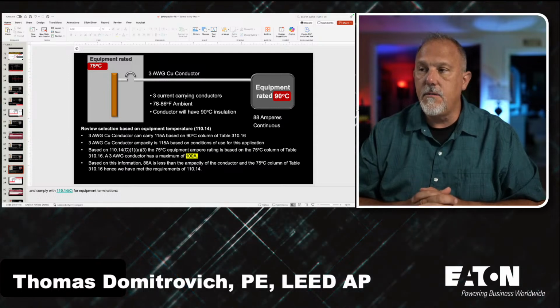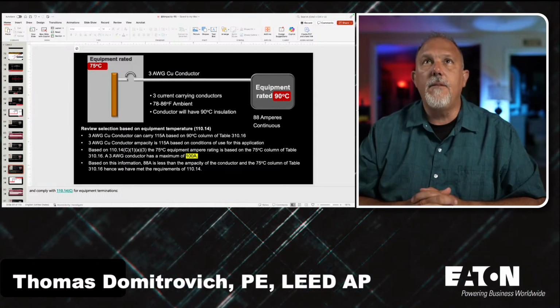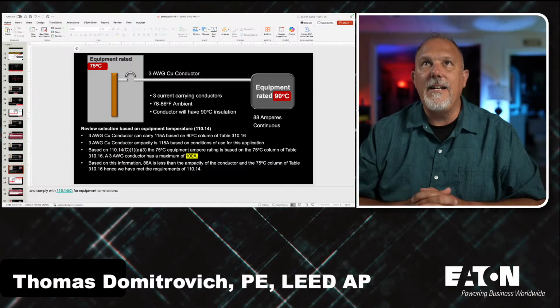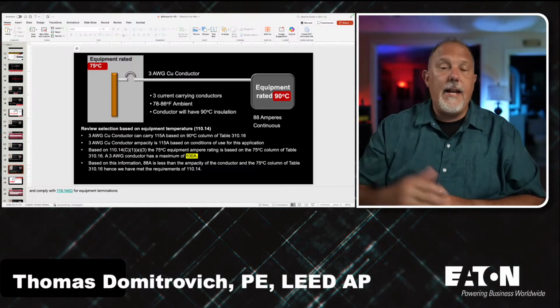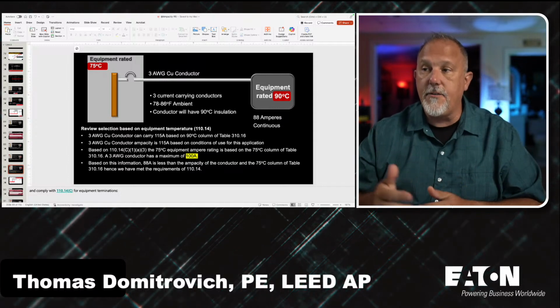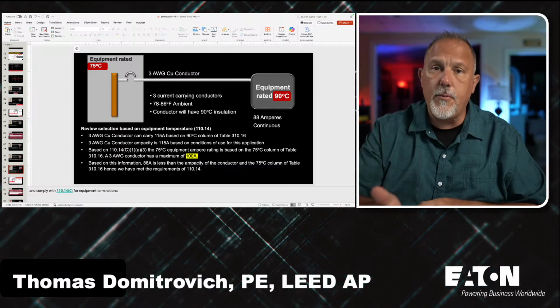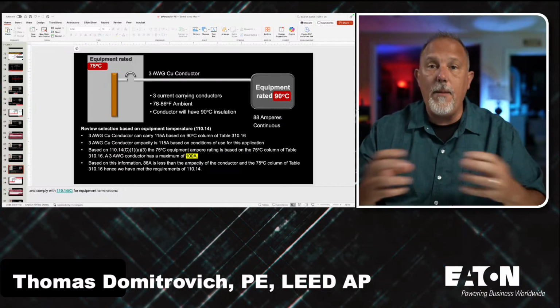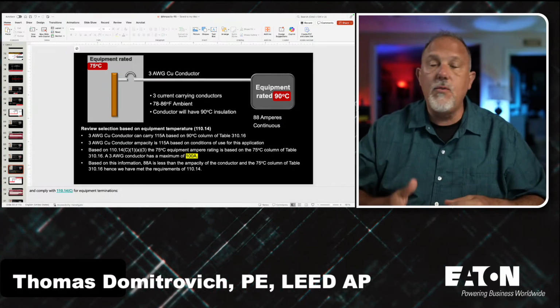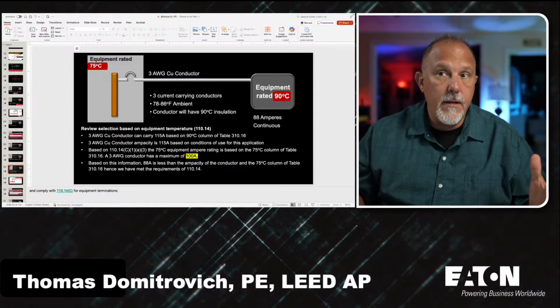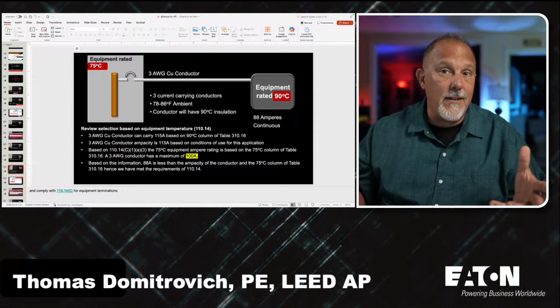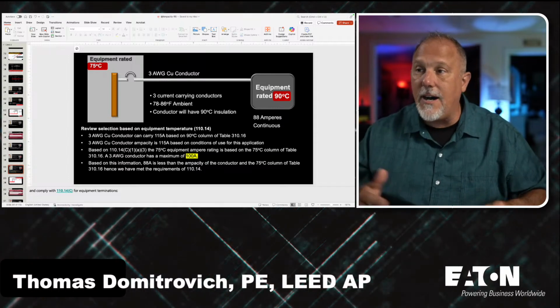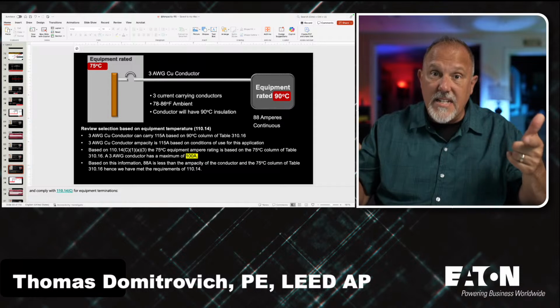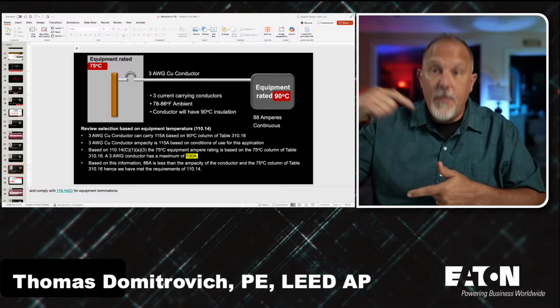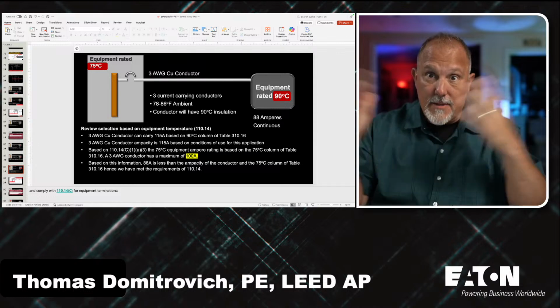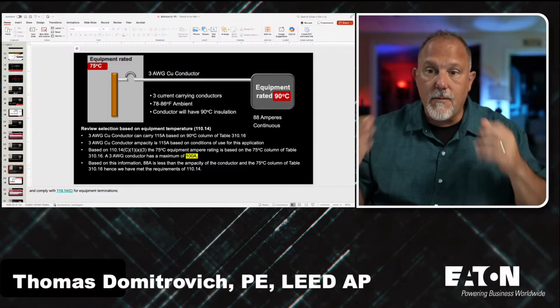Let me think about this. My termination cannot exceed 100 amps. I'm good. I have 88 amps of load, so I am good with 100 amps. I don't have to do the 1.25 because that equipment can handle up to 100 amps continuously based upon the 75-degree C column. My conductor can handle 115 amps based upon table 310.16. So I'm golden.